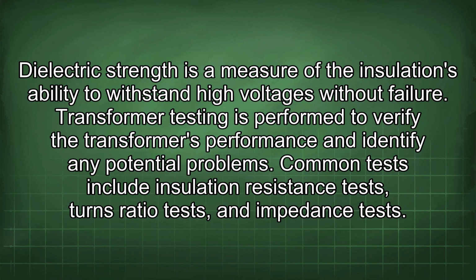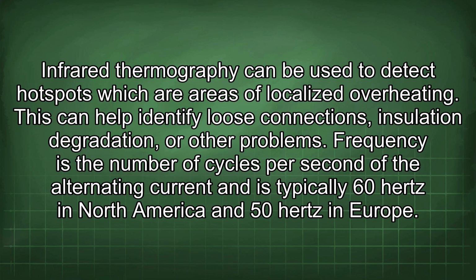Transformer testing is performed to verify the transformer's performance and identify any potential problems. Common tests include insulation resistance tests, turns ratio tests, and impedance tests. Infrared thermography can be used to detect hotspots, which are areas of localized overheating. This can help identify loose connections, insulation degradation, or other problems.